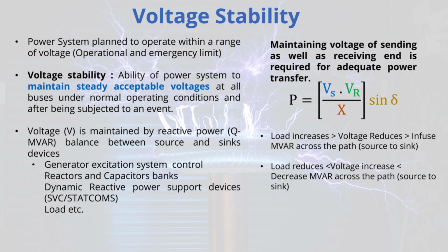And the formal definition: the system's ability to maintain acceptable voltages everywhere during normal operation and after events. How is voltage actually managed? In AC systems, voltage is primarily controlled by balancing reactive power Q, measured in MVARs. Reactive power doesn't do the work like active power, right, but it's essential for creating the magnetic fields needed to push active power through the network. You need a balance between reactive power supply and demand across the grid. So what supplies it and what consumes it?